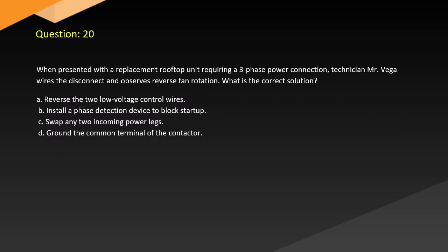Question 20. When presented with a replacement rooftop unit requiring a three-phase power connection, the technician wires the disconnect and observes reverse fan rotation. What is the correct solution? A. Reverse the two low-voltage control wires. B. Install a phase detection device to block startup. C. Swap any two incoming power legs. D. Ground the common terminal of the contactor.